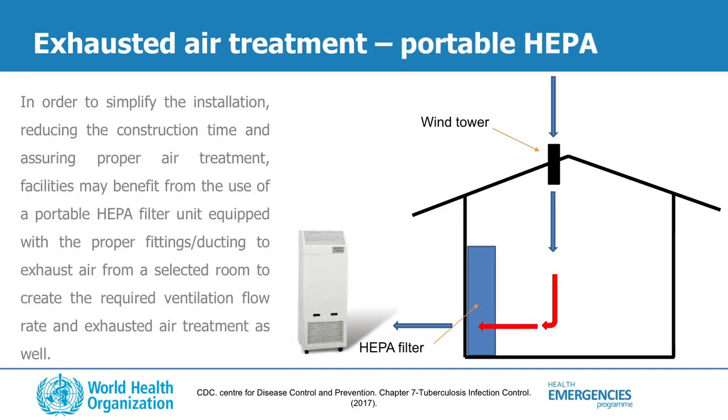In order to simplify the installation, reduce the construction time and assure proper air treatment, facilities may benefit from the use of a portable HEPA filter unit equipped with the proper fitting ducting to exhaust air from a selected room, to create the required ventilation flow rate and exhausted air treatment as well.